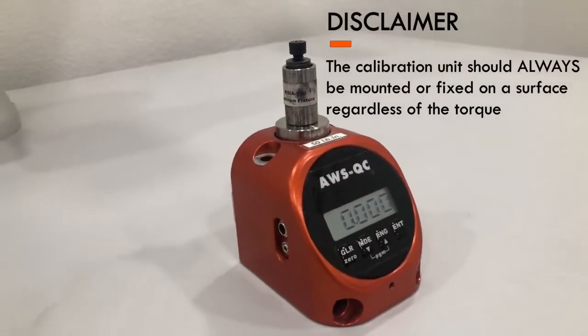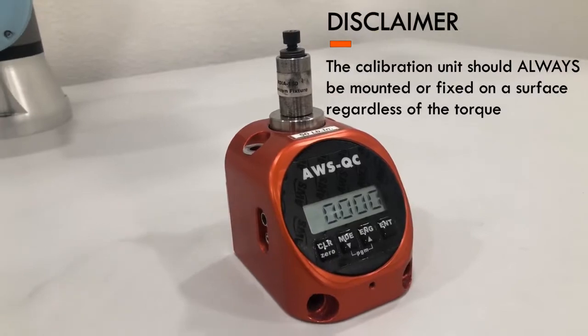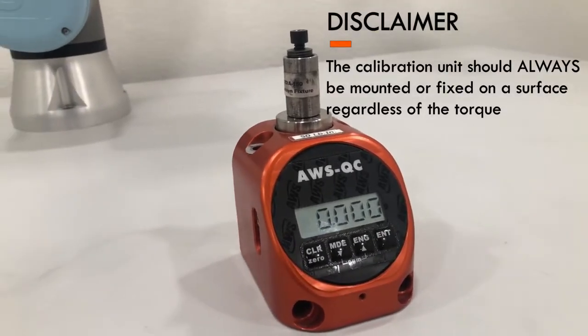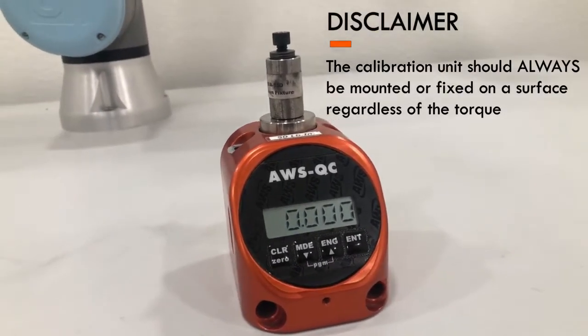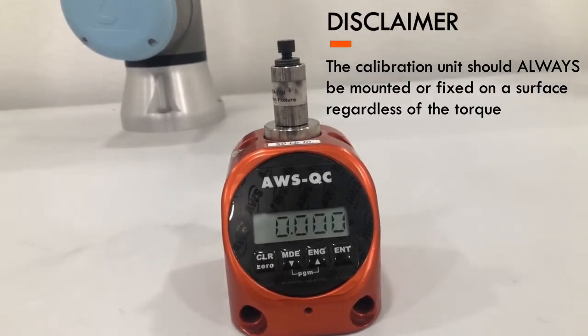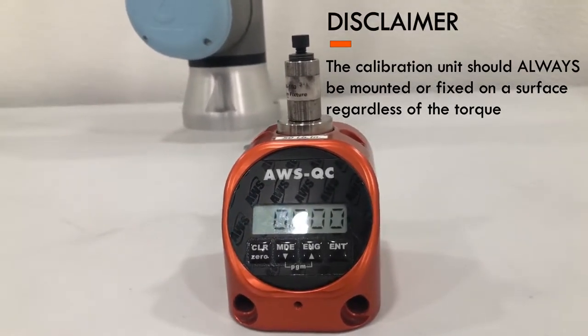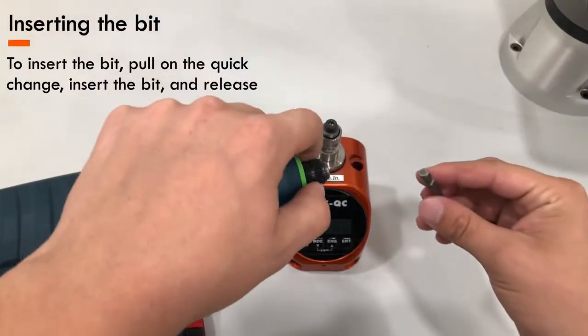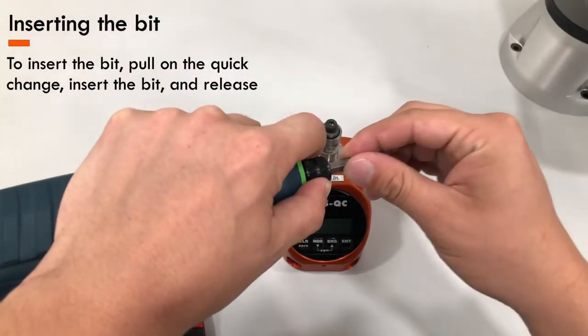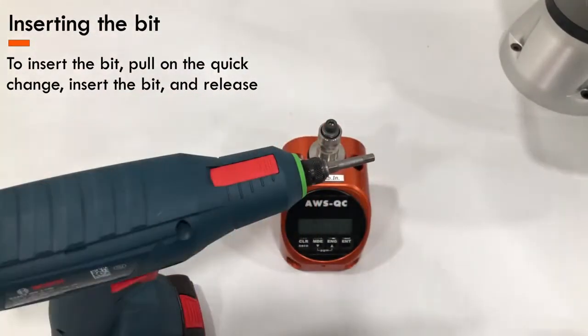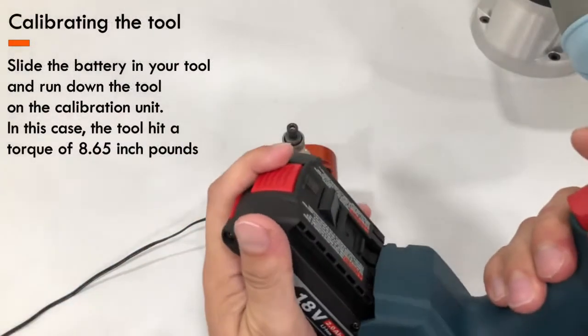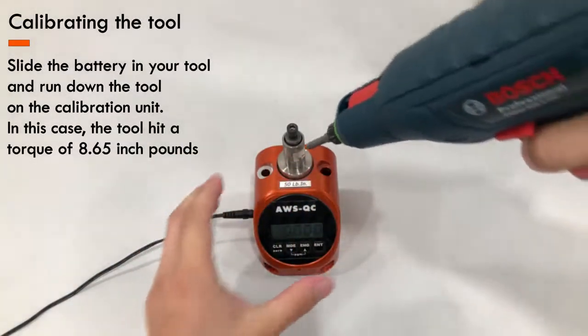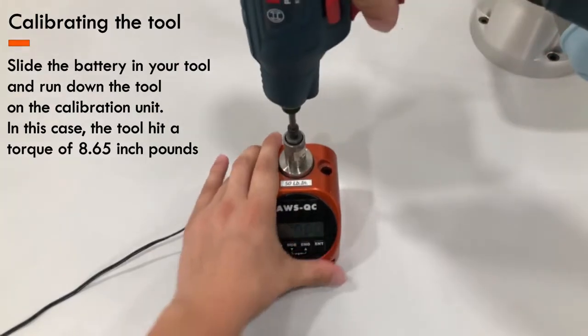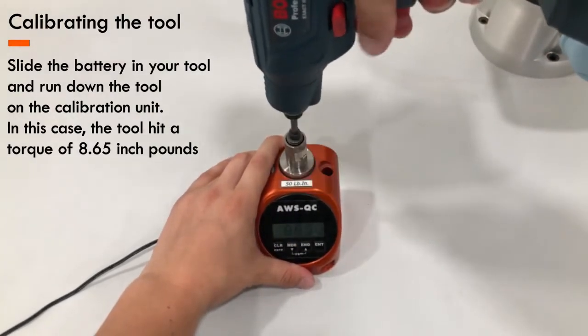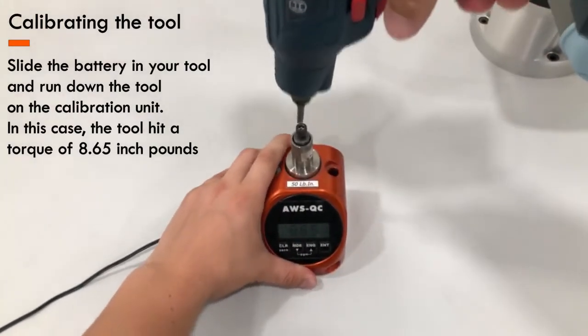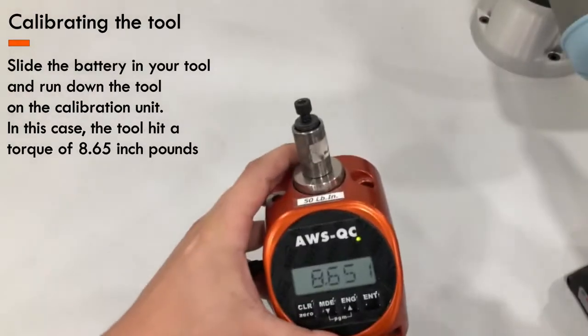Before you start calibrating, make sure that the calibration unit is mounted or fixed on a surface. For educational purposes, I did not mount the calibration unit, but you want to ensure that the calibration unit is fixed regardless of the torque. Insert the bit by pulling on the quick change, inserting the bit, and releasing. Slide the battery in your tool and run down the tool on the calibration unit to see the current torque. In this case, the tool hit a torque of 8.65 inch-pounds.